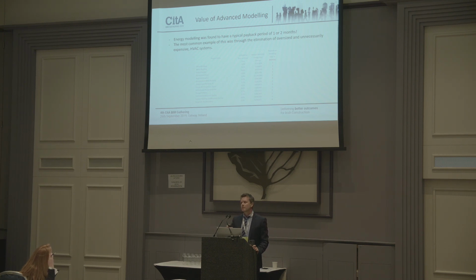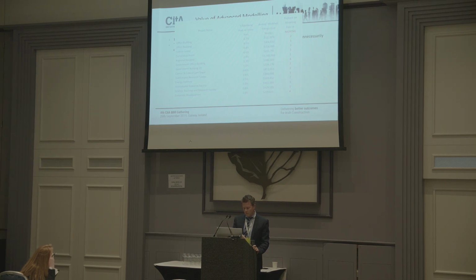So we're talking about the life costs of the building rather than capital costs - the costs saved by putting in the right systems as you run that building. They looked at a whole range of different buildings, comparing the percentage of modelling fee versus gross capital cost, which is a very small fraction. But in terms of annual modelled energy cost savings, there are some really significant savings - and that's why it leads to a 1 to 2 month payback period.